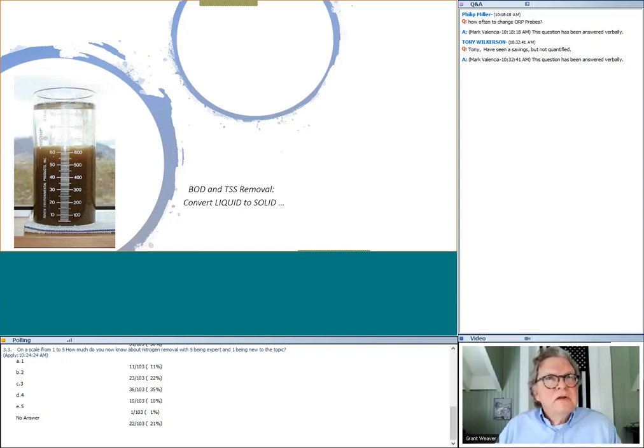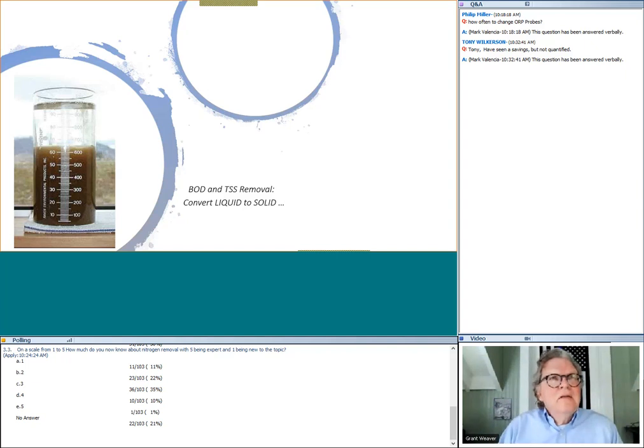This is a very different pollutant that we're removing from the wastewater. Everything except for nitrogen, and maybe some carbon, when we break it down, it goes off as carbon dioxide in the digester. But other than that, pretty much methane gas leaving the anaerobic digester. Pretty much all of our mainline treatment tankage, what it's doing is converting soluble pollutants into bacteria. Actually, a wastewater treatment plant, if you step back and think about it, other than the primary treatment where we float things, sink things, and the screening where we screen things, it's all about growing bacteria. And as the bacteria feed on the soluble pollutants, as a byproduct, really, they leave clean water.